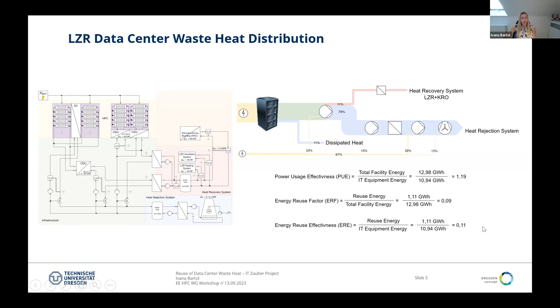Our planned solution is to connect all of the cooling infrastructure to the heat recovery system, and to connect the heat recovery system to the district heating network with the implementation of a heat pump. In this case, PUE gets slightly reduced because the heat rejection system will be mitigated. But the other two performance indicators will drastically increase, resulting in 89% of IT equipment energy being reused.